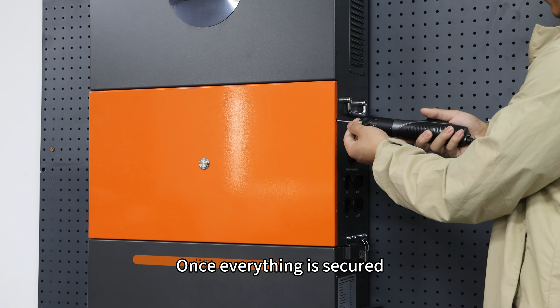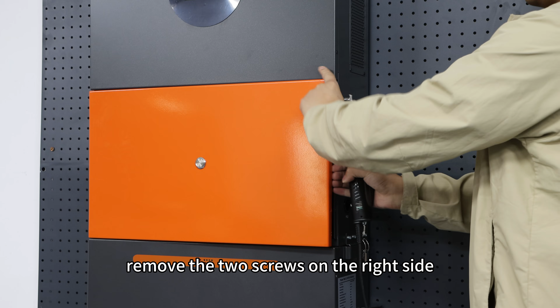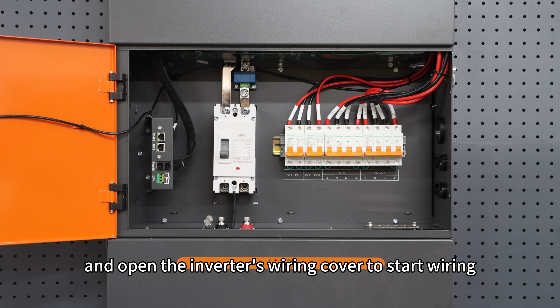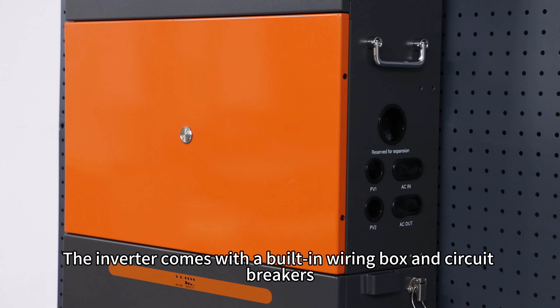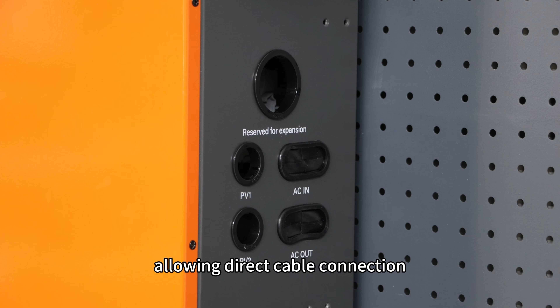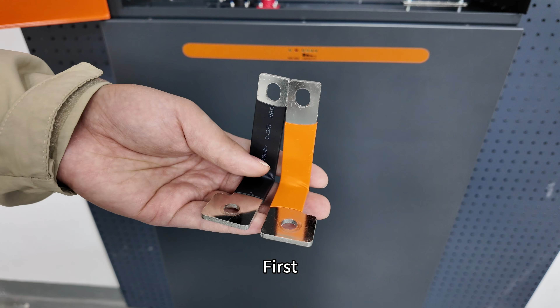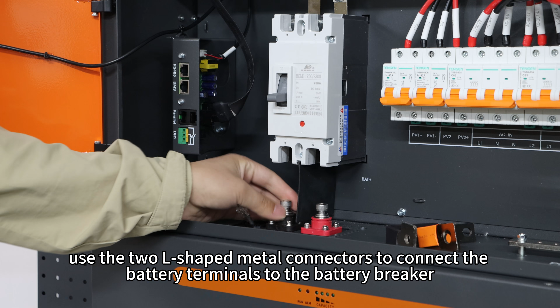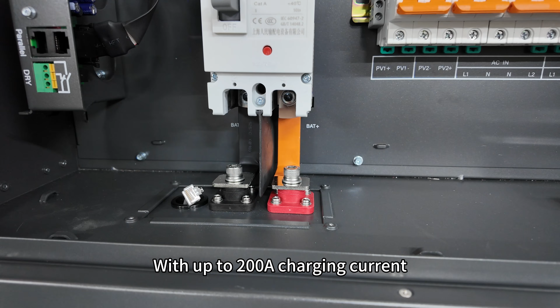Once everything is secured, remove the 2 screws on the right side and open the inverter's wiring cover to start wiring. The inverter comes with a built-in wiring box and circuit breakers, allowing direct cable connection. First, use the 2 L-shaped metal connectors to connect the battery terminals to the battery breaker. No separate battery cables are required, making installation faster and cleaner. With up to 200 amp charging current, the system enables faster battery charging under good sunlight. After connection, reinstall the terminal covers.